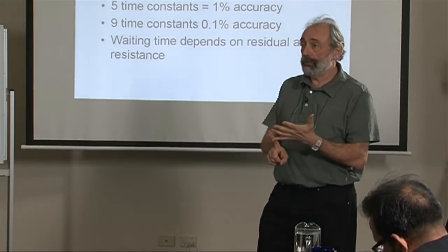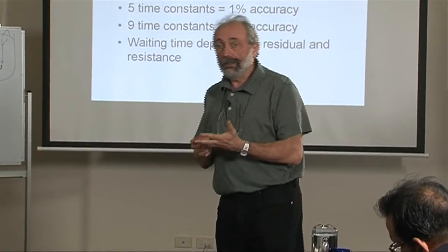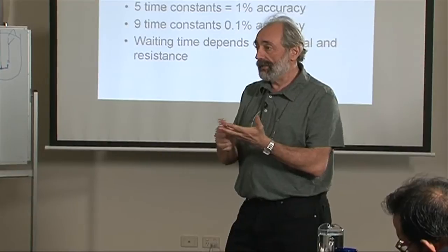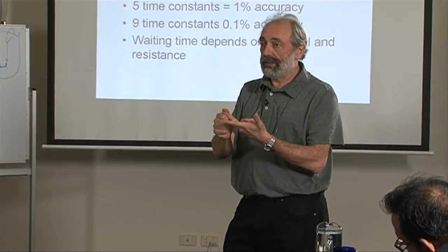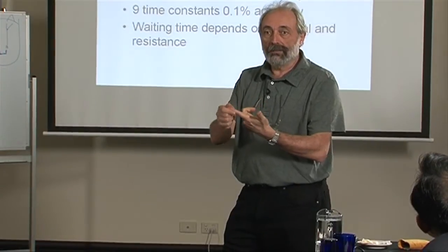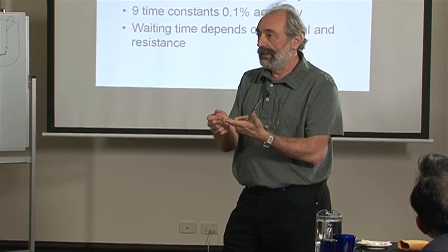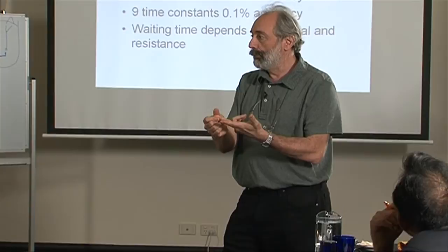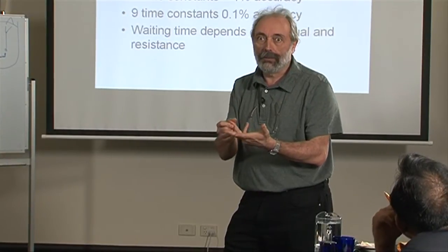You do a test on a transformer. You start in the morning. You probably do tangent delta, bushings, excitation, turns ratio, SFRA, polarization index, short circuit impedance. I don't know what else you do.